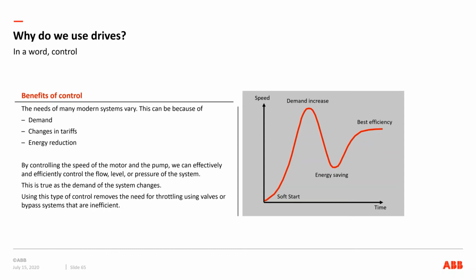Those are the kind of reasons we're looking for, because in the municipal business for water and wastewater, we have a very cyclical demand. People get up in the morning, take showers, go to the bathroom, cook breakfast, and those kind of things, so we have a big increase, and then as everybody goes to work, we have a little bit of a decrease. Then as everybody comes home from work, turns the ovens on, goes outside, waters the grass, starts working in the garden, so we have another increase. And then we have the background from industrial facilities during their peak times. So we have a very non-linear load for the demand, and that really sets itself up for variable frequency drives to give you the amount of speed, energy, or movement that you need.